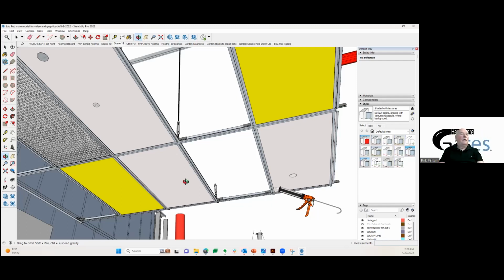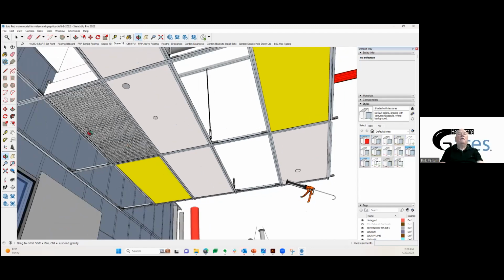To the left is the bottom of the HEPA filter. And please use clean room lights — they use this grid, and you should use nothing less than a 1.5 inch wide grid, this one's even more so, a 2-inch grid. It's wide enough that nothing fits into it, but a regular troffer light leaks like a sieve. So these are specially sized lights that are as airtight as possible.